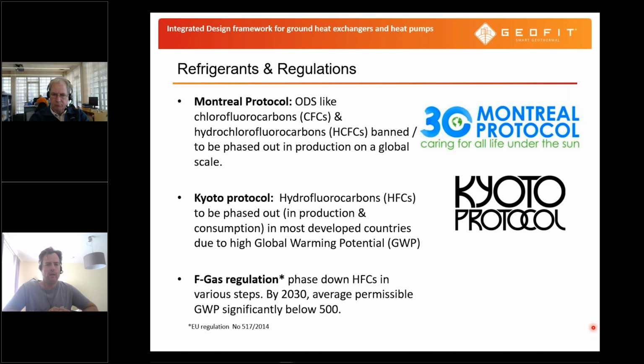One really important regulation is the so-called F-gas regulation, which deals with the phase down of refrigerants. This phase down means that by 2030 the average permissible global warming potential in a newly installed heat pump system must be significantly below 500. The global warming potential is a number which compares your global warming effect to CO2. Taking a look at conventional refrigerants which have been used in the past, we are at the level of 1,000, 2,000, or even 4,000. So this value has to go down to below 500 in several steps up to 2030. That is 8 years from now, and it comes fast.